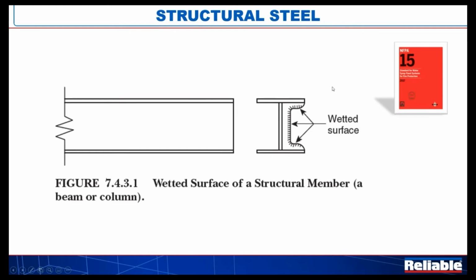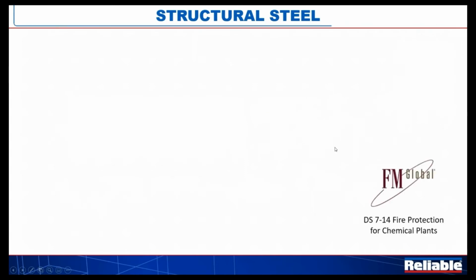Well, don't be fooled, because what this doesn't show is that protection is actually supposed to be applied to both sides of that beam or that column. So I ended up doubling my head count on that. But again, just be aware of that. This went, by behest of the AHJ, to the NFPA EOD, and they confirmed that was the intent, to actually have it on both sides.